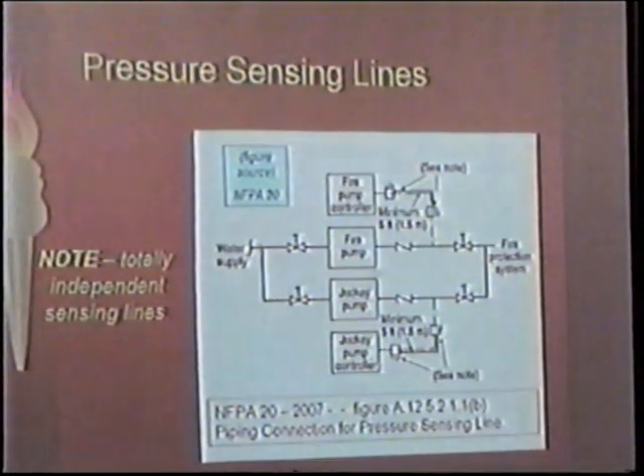And what that means when it's on the system side is that when that pressure switch needs to be maintained, you're draining the whole building down to change that pressure switch. That's why the code has it between the control valve and the check valve, so that you don't have to do that. That way we can just isolate the pump and maintain that pressure switch for that unit. And also that you may allow the bypass to be active too. Depending on where that comes off, if it's not in the right spot, you may have to shut your bypass off too while you're servicing the pump.